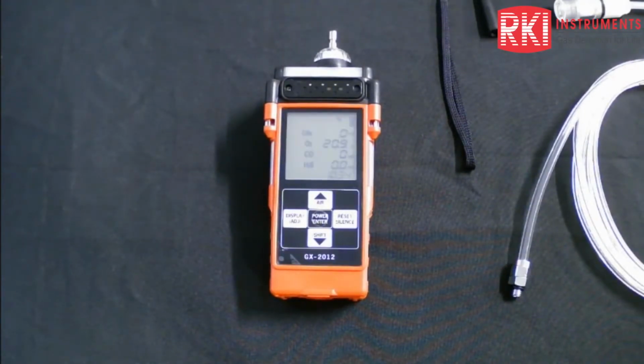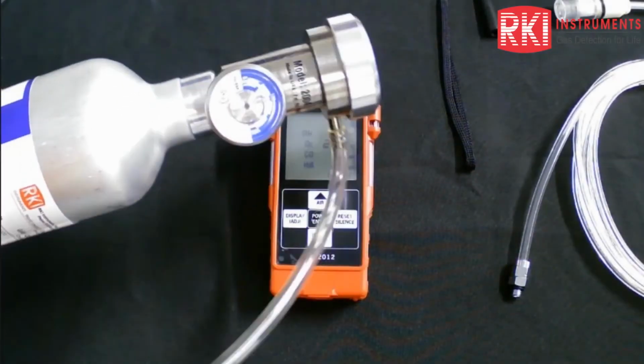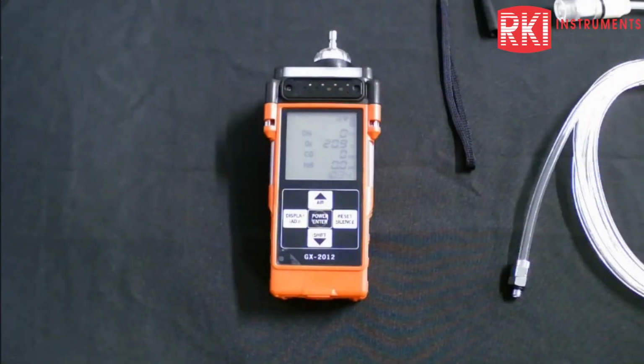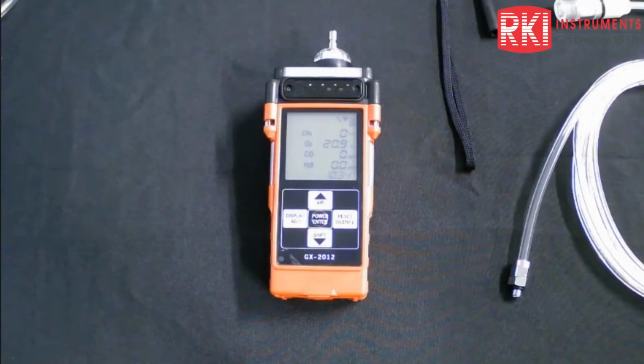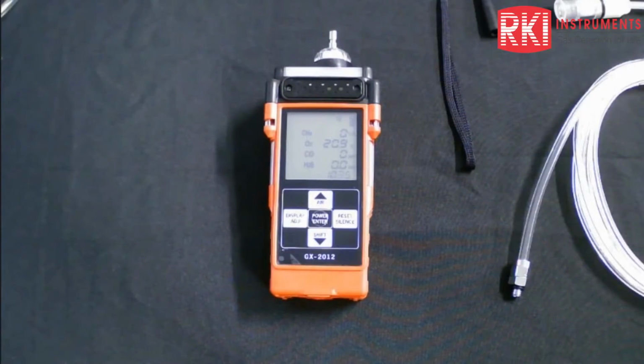It's going to add to the life of your pump if you do use a demand flow regulator. What we have seen, and what you will see if you use a traditional regulator that you turn the valve on and off and allow gas to escape, is that those regulators can have different liters per minute flow. We generally pull a sample at about half a liter when we use our pump. Now you may say, hey, I have a regulator that I can turn the valve on and allow the gas to flow through. Yes, you can do that, but it's not suggested, because you're pushing air through the pump rather than letting the pump pull it. It's going to do a little bit of damage to the pump, and over a long time you're going to see it being negative. The other aspect is if you're not sure what the flow of that regulator is, you will not get an accurate calibration.